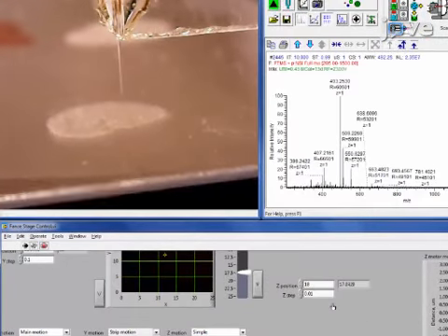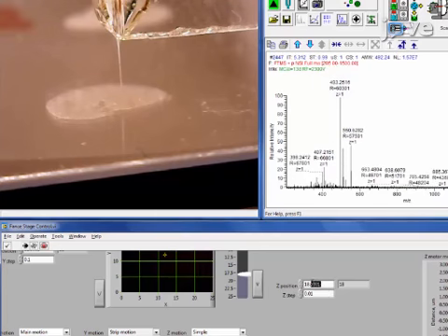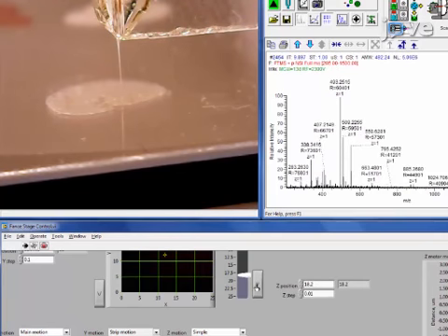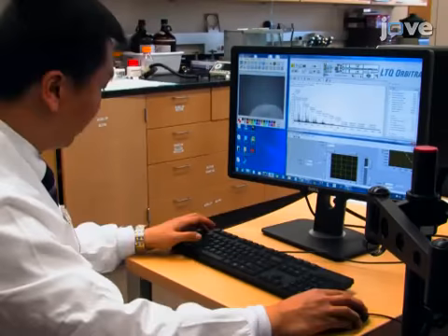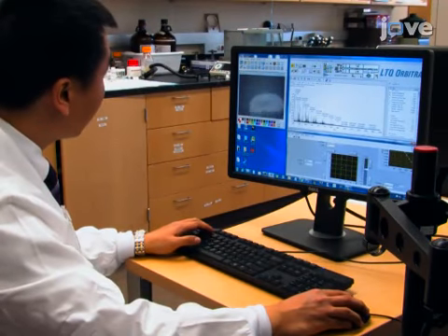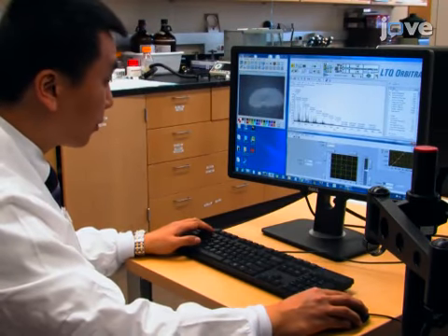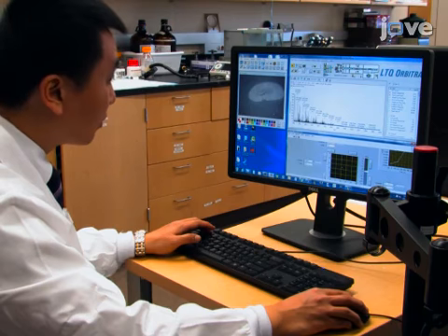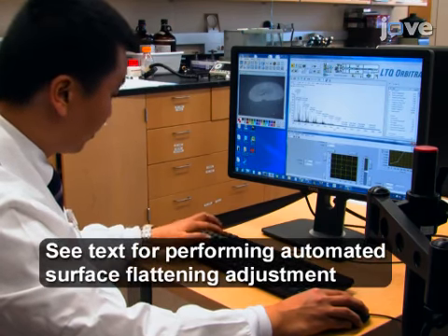Adjust the height of the single probe so that it is resting just above the surface of the sample and able to perform surface extraction of metabolites. Carefully lift the Z stage and then use the USB digital microscope to monitor the distance change between the single probe tip and tissue surface.